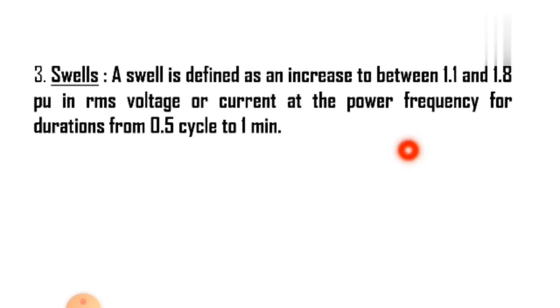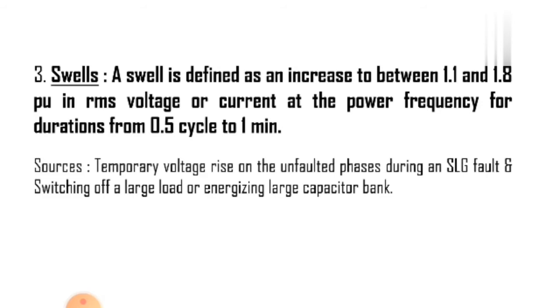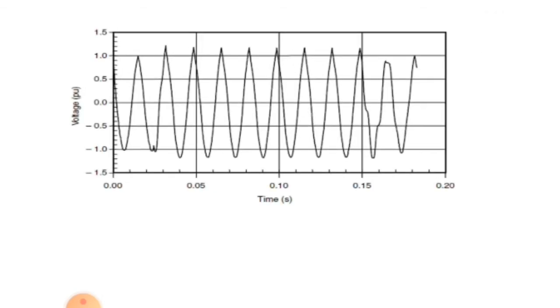The last category is swells. It is defined as an increase to between 1.1 and 1.8 per unit in RMS voltage or current at the power frequency for a duration from 0.5 cycle to 1 minute. As with sags, swells are usually associated with system fault conditions but they are not as common as voltage sags. One way that a swell can occur is from the temporary voltage rise on the unfaulted phases during a single line to ground (SLG) fault. This plot illustrates a voltage swell caused by an SLG fault. Swells can also be caused by switching off a large load or energizing a large capacitor bank.